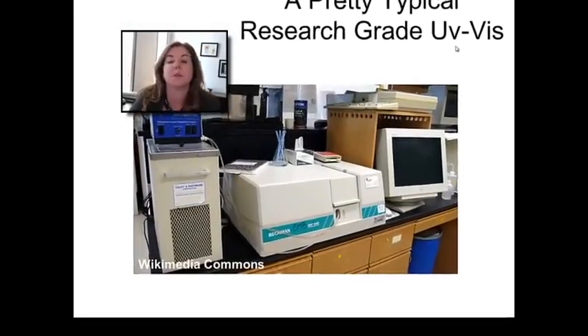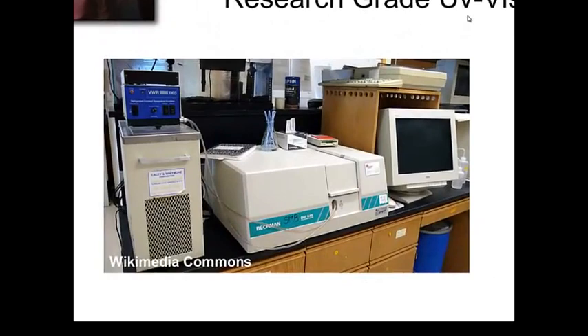So here's a pretty typical research grade UV-Vis. They're found all over the place, and most research labs have them. They're not that big. They have a computer attached. In this case, there's a flow system, a flow cell setup, so they're doing a kinetic measurement versus time. But as you can see, it's a pretty straightforward instrument.